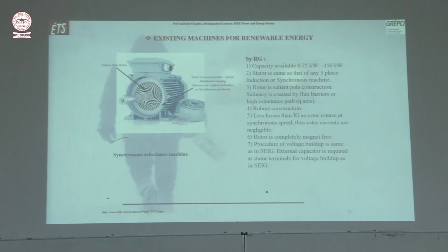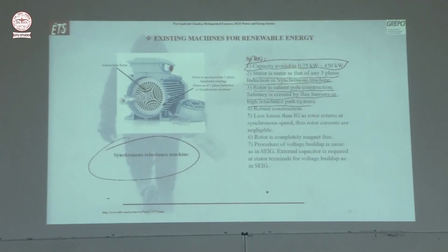And then another type of machine, synchronous reluctance machine, which is becoming very popular, and it's available in this capacity, 0.75 kilowatt to 450 kilowatt, made by ABB. I think now ABB, at some places they have changed the name Hitachi Energy, but perhaps this motor. So this has lot of advantages. Stator is same as that of 3-phase induction machine or synchronous machine. Rotor is salient pole construction. Saliency is created by the flux barrier of high reluctance path. So you see, these are flux barriers here, which creates the saliency here.